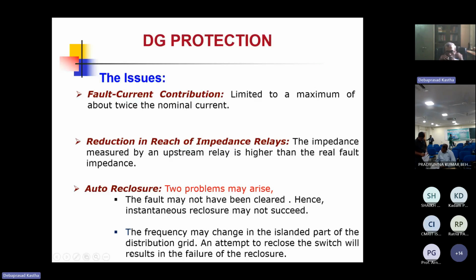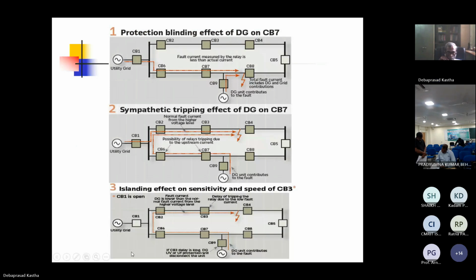So these are some of the problems when you come to protection of a distribution network when DGs are present. Let us see. The first case shows a situation where you have the utility grid coming through this and there is a DG unit here and there is a fault before this CB8. The problem is that CB7 sees the fault current contribution only from the grid. It does not see the fault current contribution from the DG. So even if it is a severe fault, this CB7 may not trip.